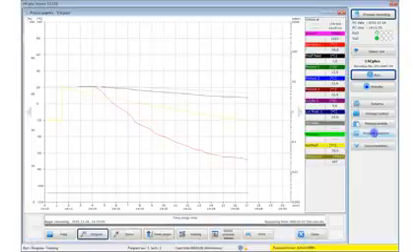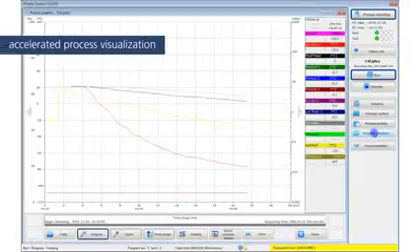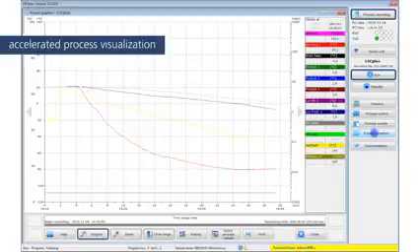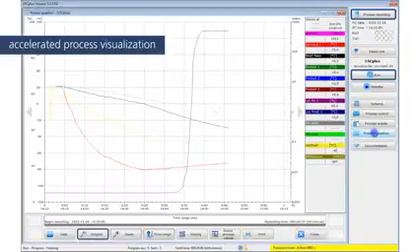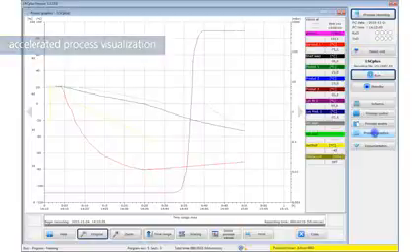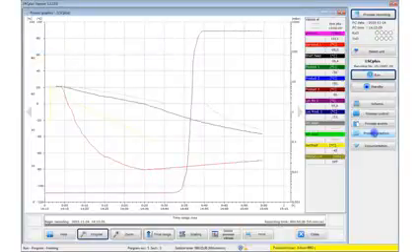The software LPCplus records all process data from the start of the process until the process recording is stopped at the end of the freeze drying process. It is displayed in a process graphic where you can view data during the course of the process, such as the vacuum level, the ice condenser temperature, or the product temperature. The current numerical values are also shown in a table next to the graphic.